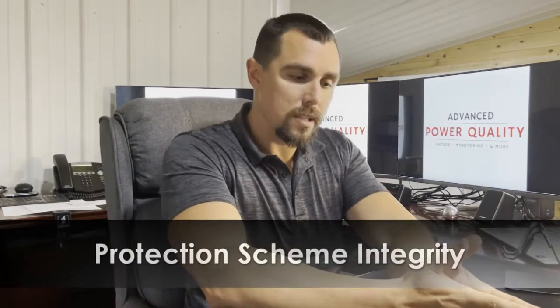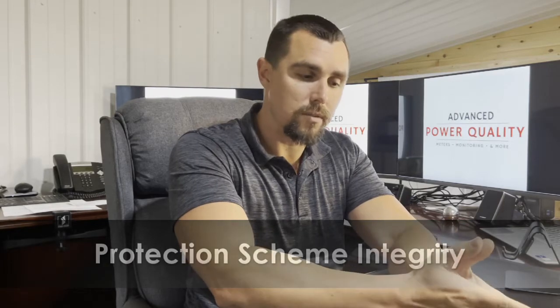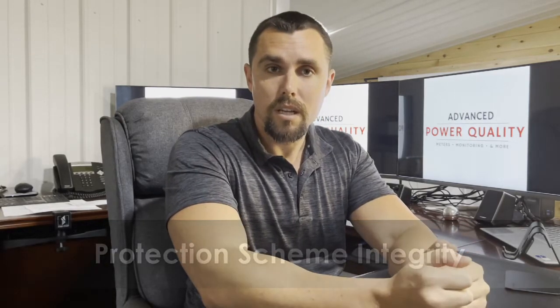For our system planners: whenever you see a large solar farm or a large subdivision requiring residents to install solar panels, this may impact your protection scheme. What I mean is, our protection scheme is all fault current based—based on fault current magnitude and duration. Currently, it's all based as if fault current was provided from one source, the substation.